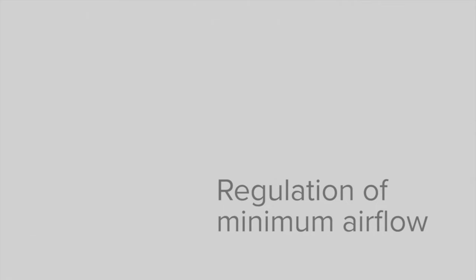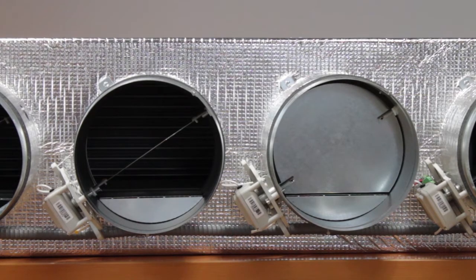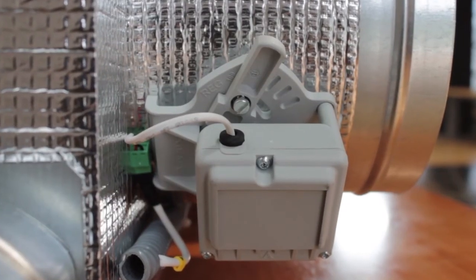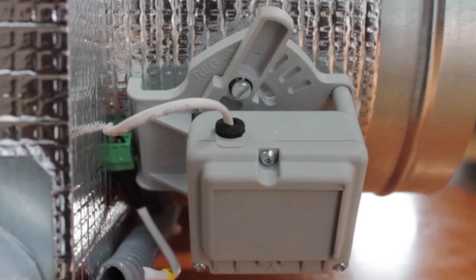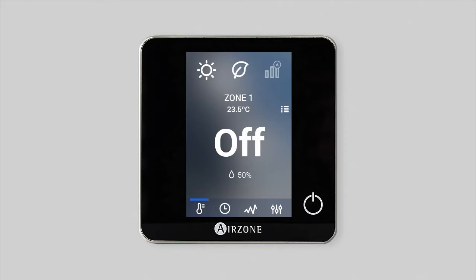Regulation of minimum airflow: each damper in the motorized plenum also has an adjustment for minimum airflow which can be configured so that each zone also receives a minimum airflow supply from the AC unit. This is adjusted with the damper open and ensuring that more than one zone has demand.